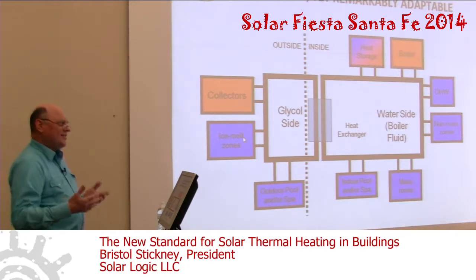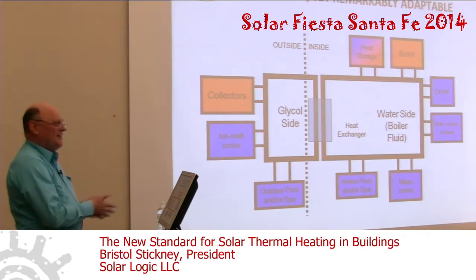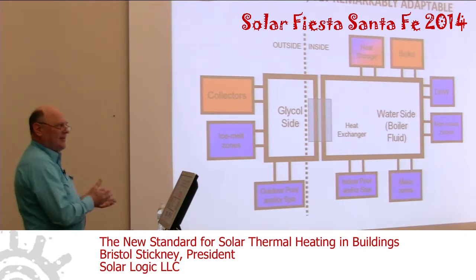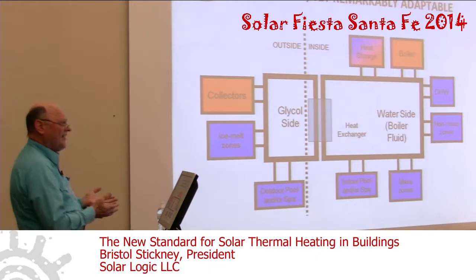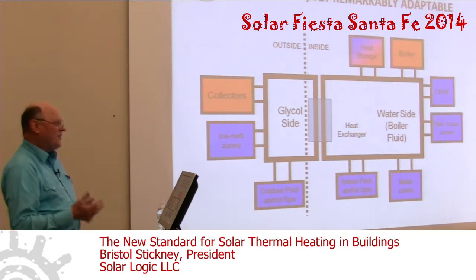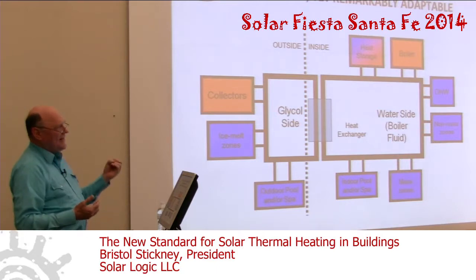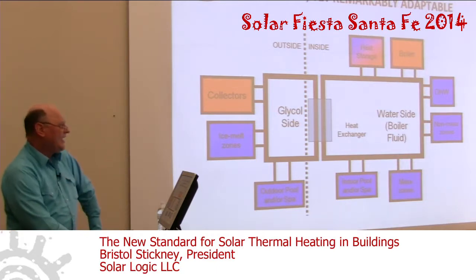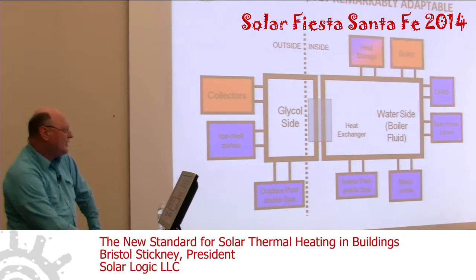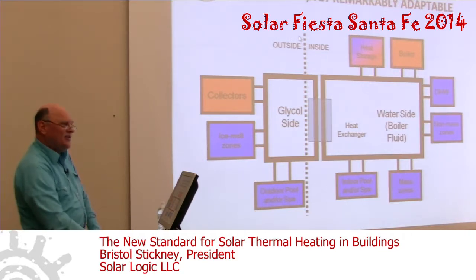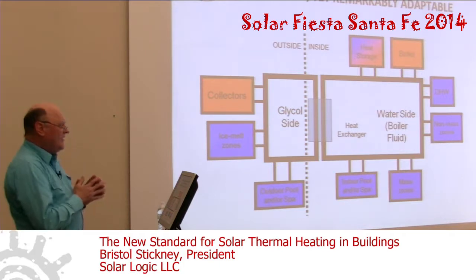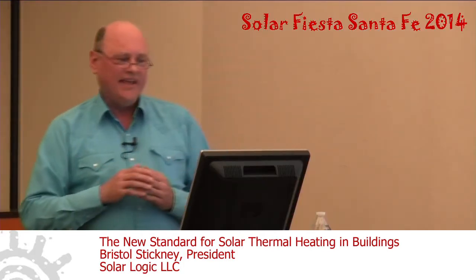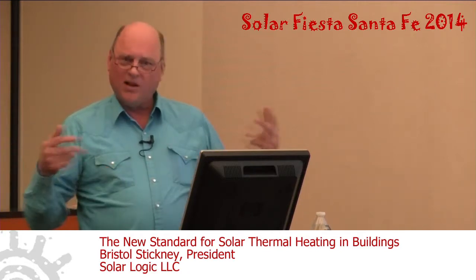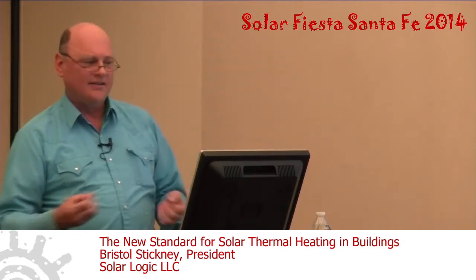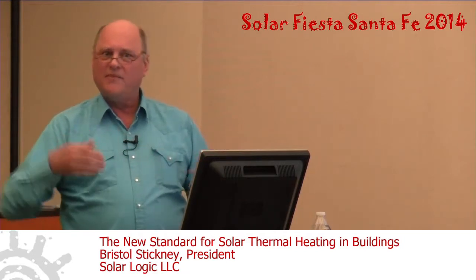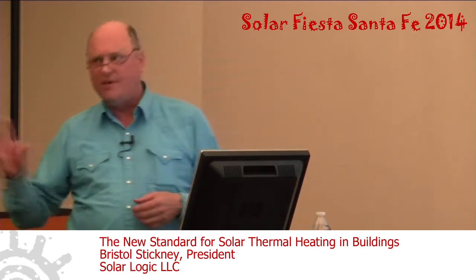And of course, since the tubing in the sidewalk that melts the ice is outdoors and is in danger of freezing, it has to have glycol in it. So we use the same glycol that we use in the solar collectors for both collecting heat and giving heat out. Distributing heat and collecting heat is done with the same fluid. So that, in a nutshell, is the new standard in hydronic heating. If you follow this standard and you don't deviate from it, you will find that you can plug things in and unplug things as you're designing a system. You can plug things in or unplug them as you're applying this to different buildings.